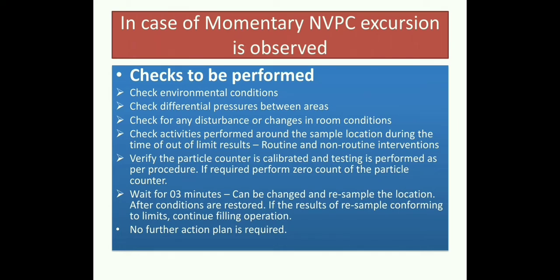First, we need to check the environmental conditions — whether temperature, RH, and pressure differences between the areas are accurate as per qualified area requirements. Disturbed air differential pressures may allow particles to enter clean rooms. We also need to check for disturbances in room conditions and check for routine or non-routine interventions performed at the time of excursion, as these interventions may contribute to momentary excursions.